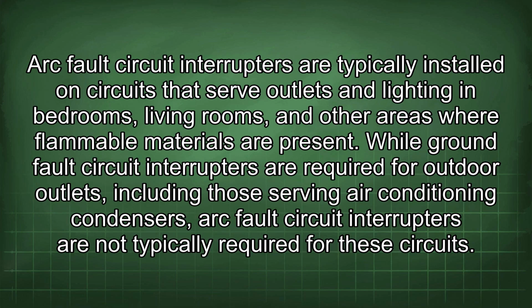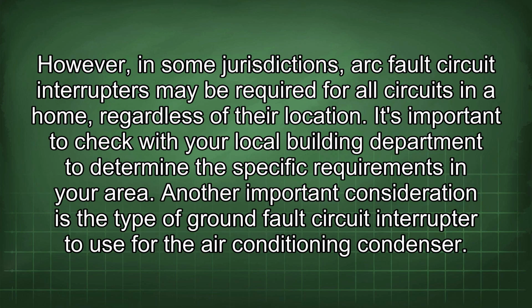Arc fault circuit interrupters are typically installed on circuits that serve outlets and lighting in bedrooms, living rooms, and other areas where flammable materials are present. While ground fault circuit interrupters are required for outdoor outlets, including those serving air conditioning condensers, arc fault circuit interrupters are not typically required for these circuits. However, in some jurisdictions, arc fault circuit interrupters may be required for all circuits in a home, regardless of their location. It's important to check with your local building department to determine the specific requirements in your area.